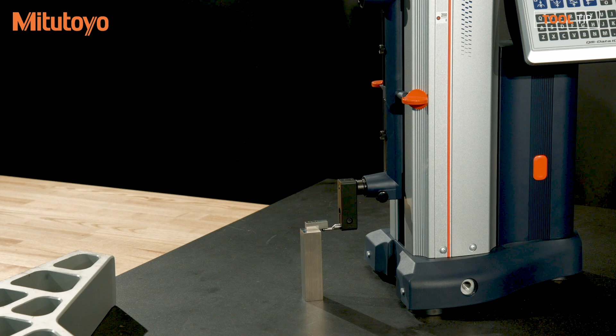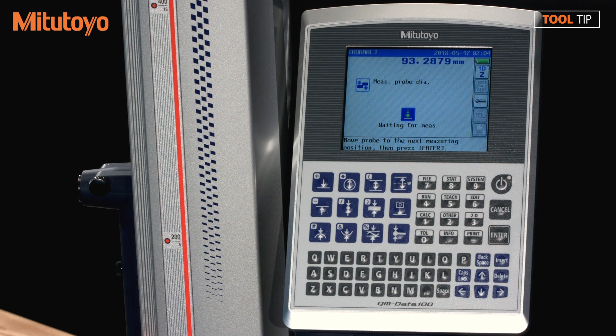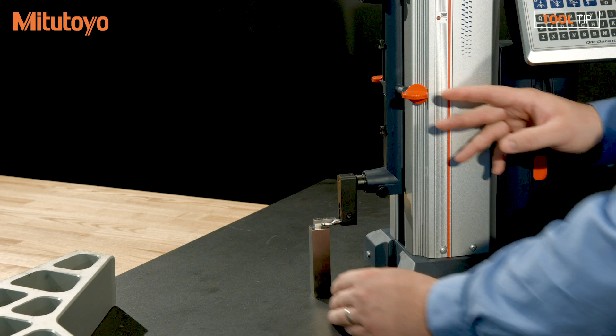Now it wants me to set the probe and the absolute origin. So let's go ahead and do that. I'm going to hit the probe calibration button, and then select method 2, which is using the included artifact. Now the machine will automatically go up and measure the bottom of the artifact. As you can see on the screen, it now wants me to position the probe so that I can measure the top of the artifact. So I'm going to move it. Once the probe is in position, I'm going to press the enter key to continue. As you can see now, the probe diameter measures 4.9940, so the probe diameter has been calibrated.